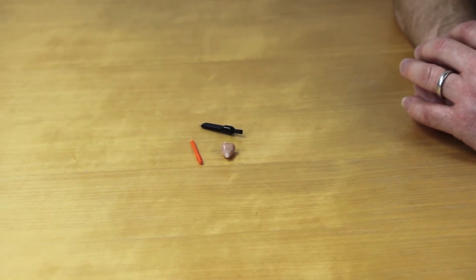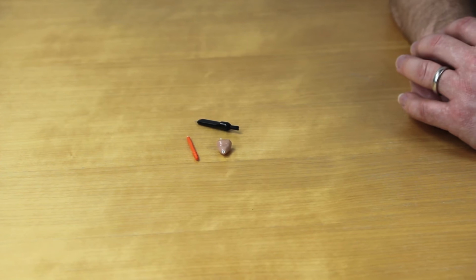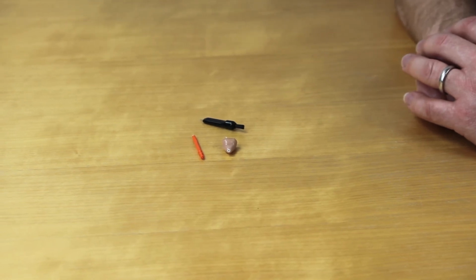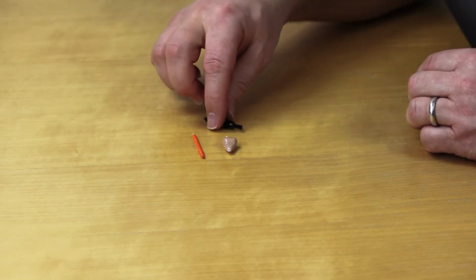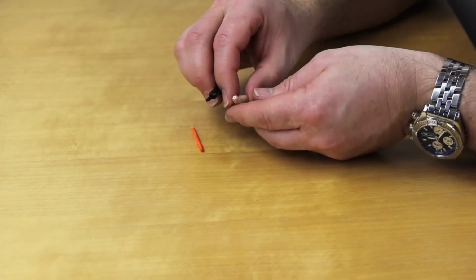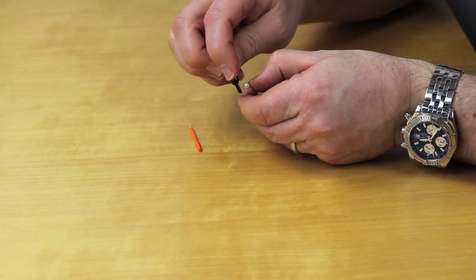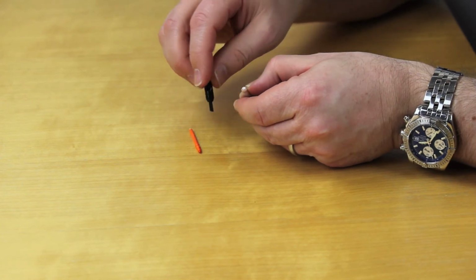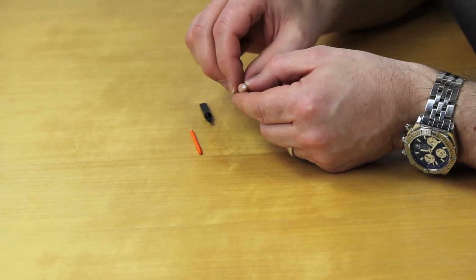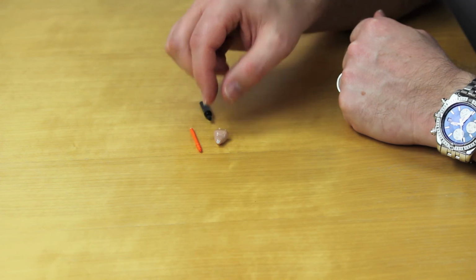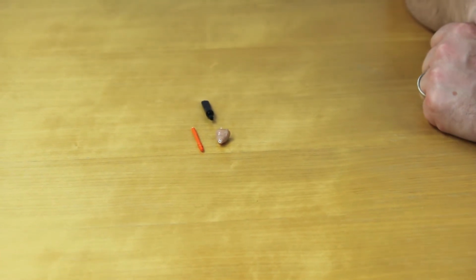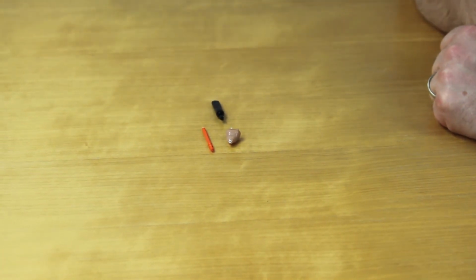It is very important to check that the wax filter is clean before every use. Use the soft brush supplied with your HD250 to brush away any accumulated debris. The wax guard will need replacing regularly. Exactly when this is required will vary considerably from person to person. We work on an average of every 4 to 6 weeks.